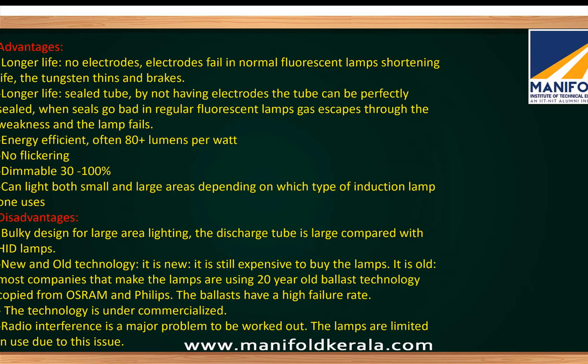Read out these advantages and disadvantages. Okay, so one of the main disadvantages is that this is not widely used technology because of the cost and because the ballasts have a high failure rate. This technology is not widely commercialized, so you cannot find these induction lamps in a wide variety of applications. The major problem is the high failure rate of chokes and electromagnetic interference because of the presence of the electromagnet.